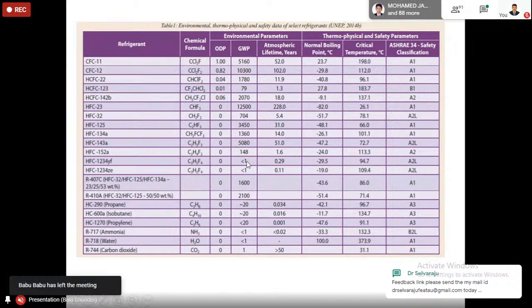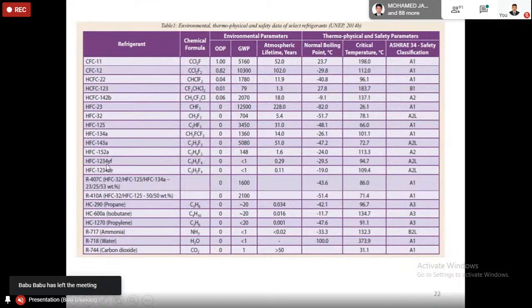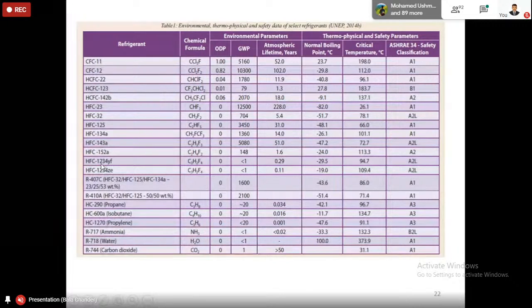There are a few refrigerants with very low GWP, something like 1234YF. This is in the olefin category, it comes under HFC or olefin category. There's also 1234ZE. This is produced by DuPont, and they claim it has very low GWP. It was introduced a few years back, maybe 5 years before, but it has not been commercialized because of its cost. 1234YF is being used for refrigerators or as a replacement for 134A.